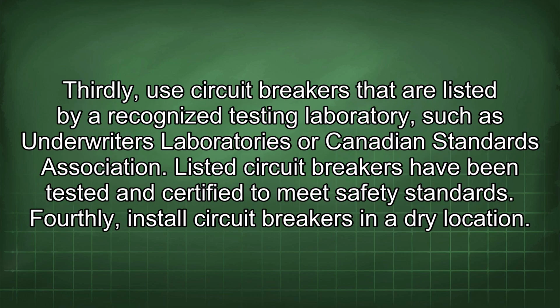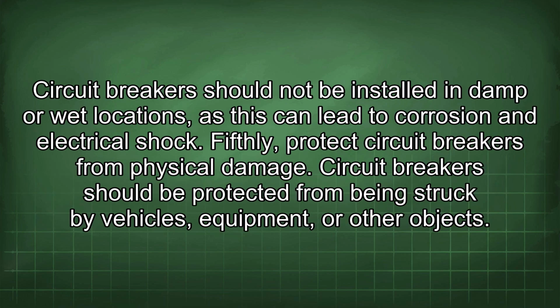Thirdly, use circuit breakers that are listed by a recognized testing laboratory such as Underwriters Laboratories or Canadian Standards Association. Listed circuit breakers have been tested and certified to meet safety standards. Fourthly, install circuit breakers in a dry location. Circuit breakers should not be installed in damp or wet locations, as this can lead to corrosion and electrical shock. Fifthly, protect circuit breakers from physical damage. Circuit breakers should be protected from being struck by vehicles, equipment, or other objects.